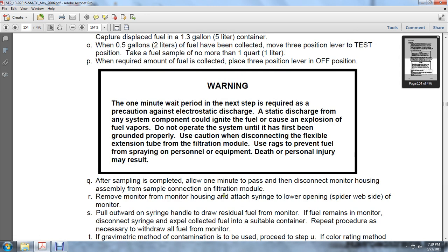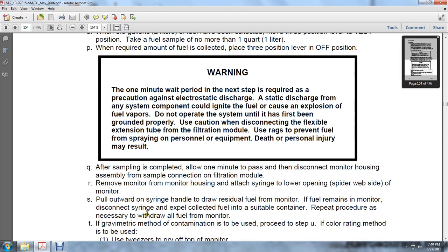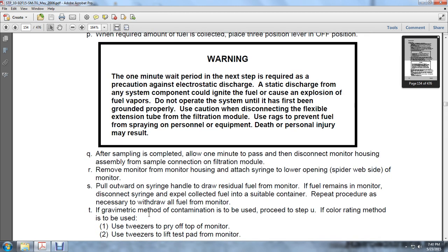Remove the monitor from the monitoring housing and attach the syringe to the lower opening, the spider web side of the monitor. Pull outward on the syringe handle to draw the residual fuel from the monitor. If fuel remains in the monitor, disconnect the syringe and expel the collected fuel into a suitable container. Repeat the procedure if necessary to withdraw all fuel from the monitor. If the gravimetric method of contamination is to be used, proceed to the next step.